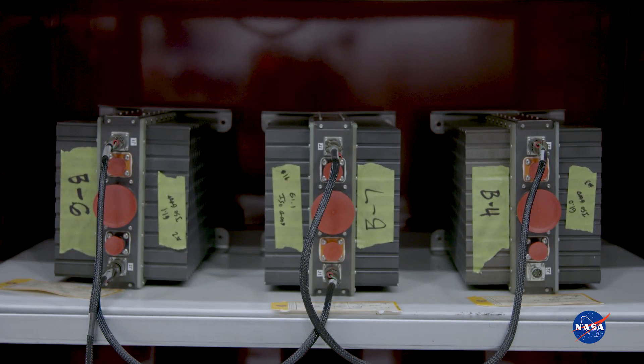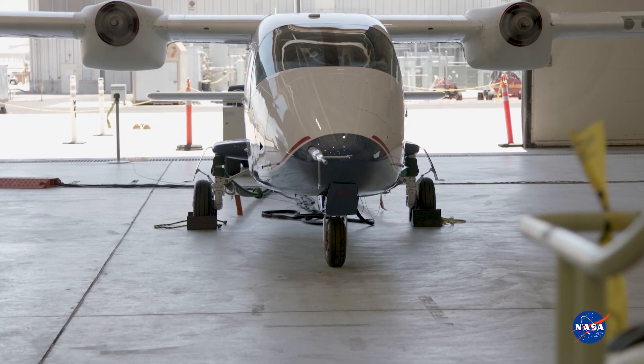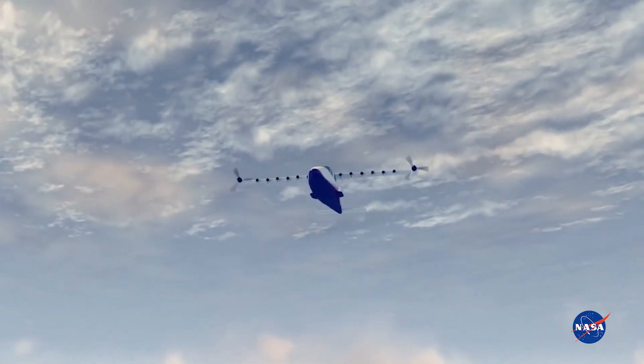There are 16 modules — two packs of eight — and that is where ultimately we'll be able to take it to our next phase of testing where batteries power the aircraft, we run the motors, and we do our formal verifications on the system before moving on to the high-speed taxi and our first flight.